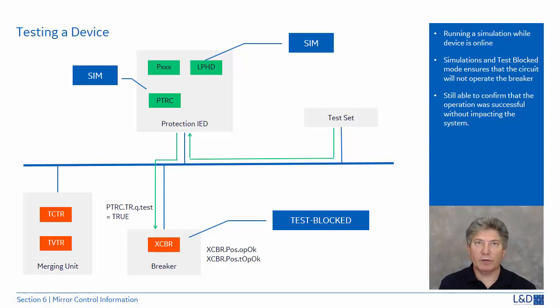The TRIP is sent as a GOOSE message with the quality flag of the TRIP signal set to test. The XCBR will receive and process that TRIP.